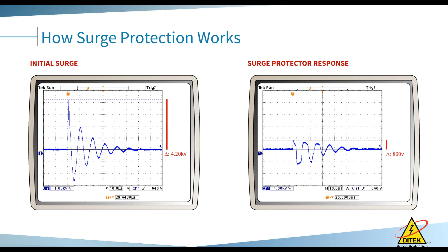Going to the components in these devices, those of us that have been around for a bit remember the old MOV devices? That's what everything had 15 or 16 years ago when we started. Now everything's progressed on all of our AC products to thermally protected metal oxide varistors, which have a high surge current rating. They have an internal safety disconnect, which keeps them from getting hot and melting and smoking like we used to see in the past, and it degrades slightly after each transient. So we've gotten a lot safer in 15 years.